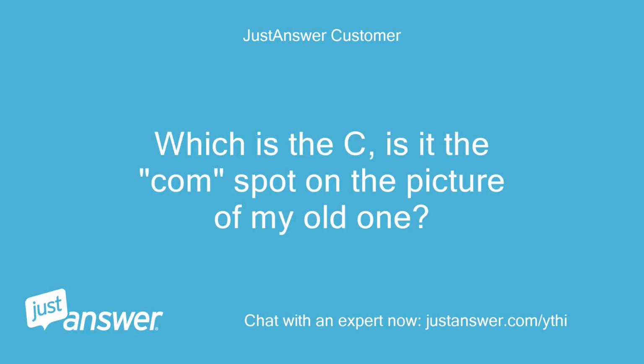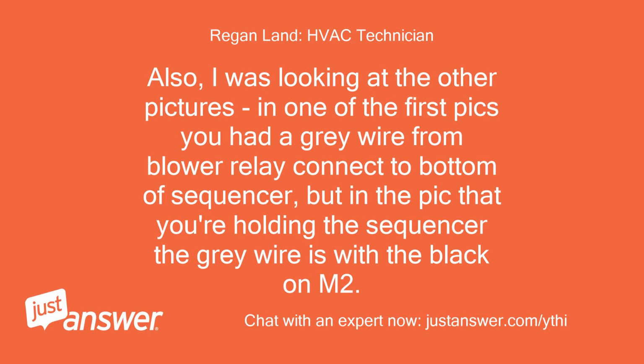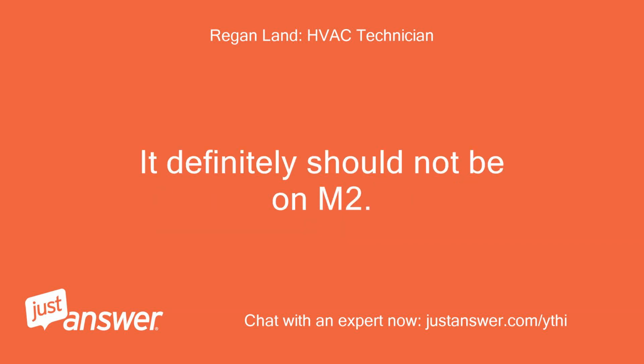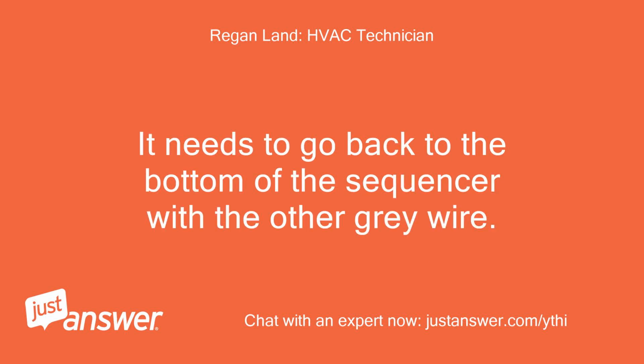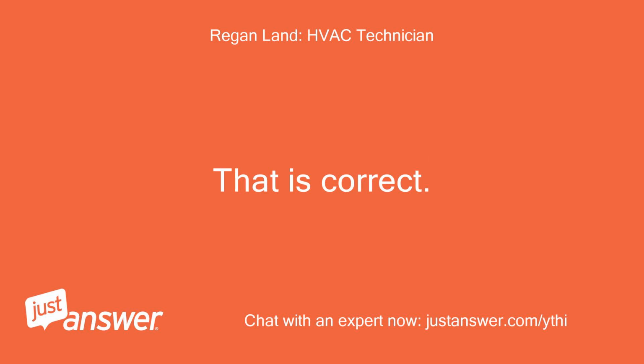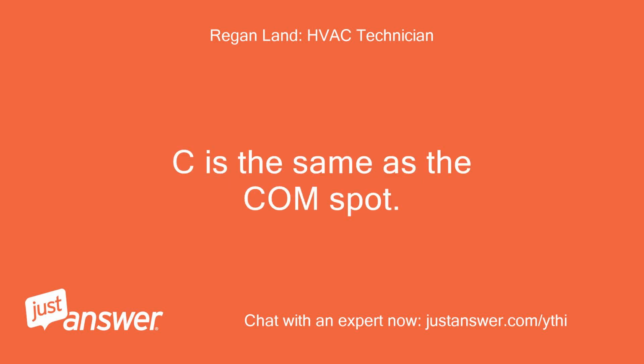Which is the C? Is it the COM spot on the picture of my old one? Also, I was looking at the other pictures. In one of the first pics you had a gray wire from blower relay connect to bottom of sequencer, but in the pic that you're holding the sequencer the gray wire is with the black on M2. It definitely should not be on M2. It needs to go back to the bottom of the sequencer with the other gray wire. That is correct. C is the same as the COM spot.